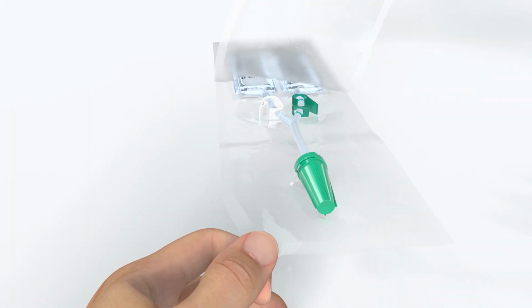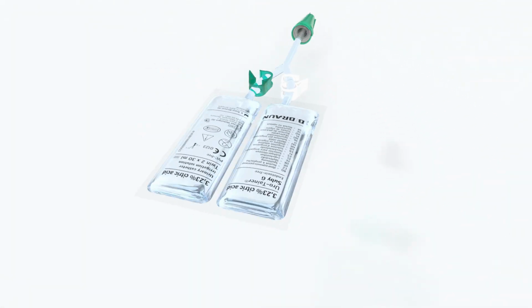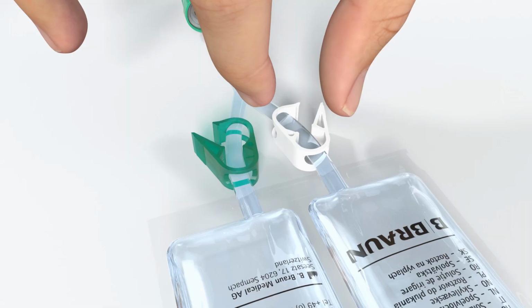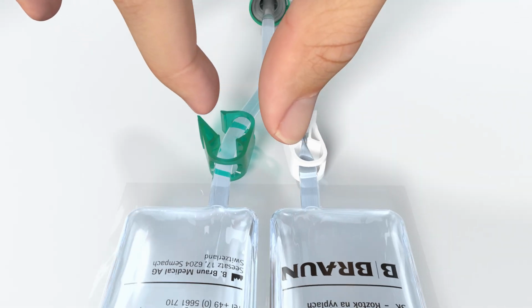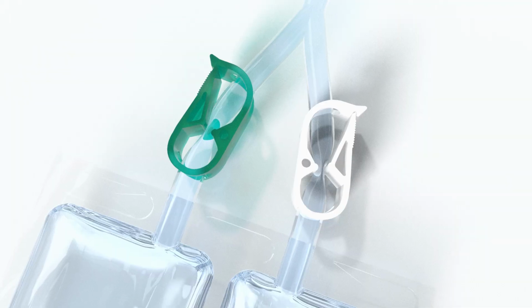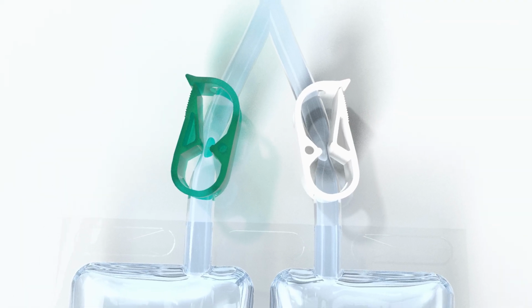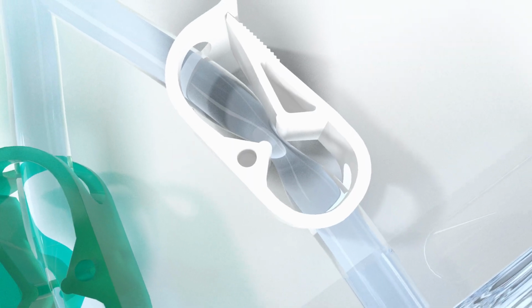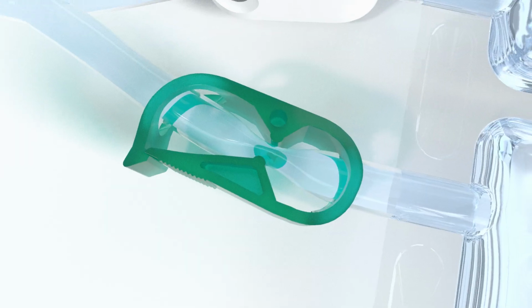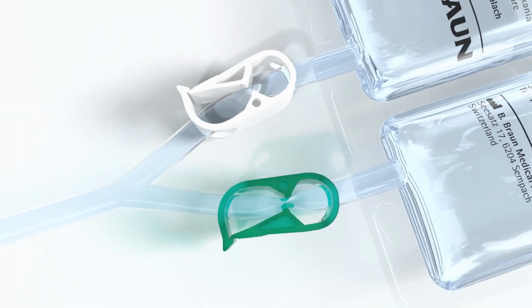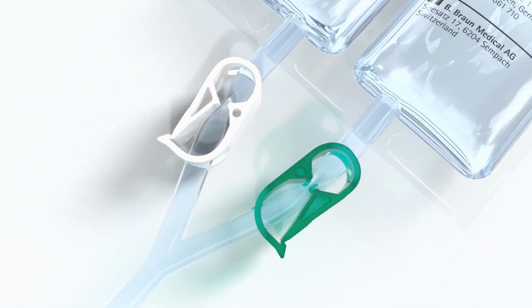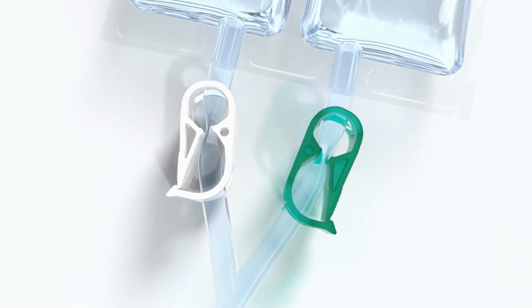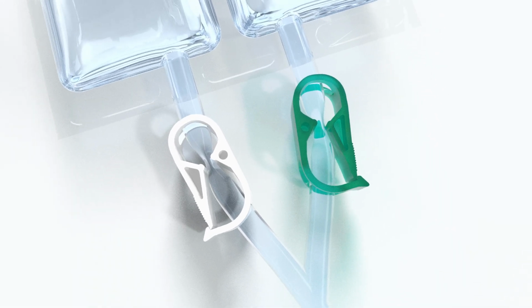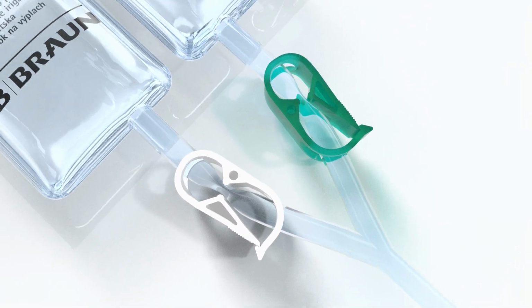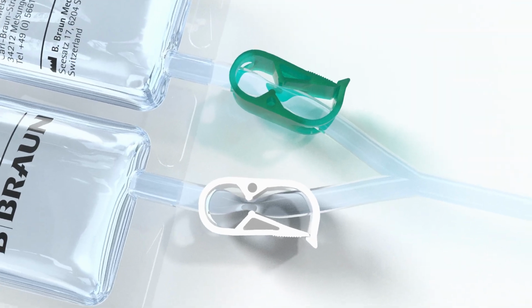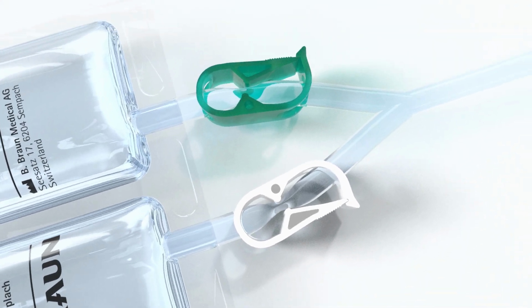Peel open the plastic overwrap and remove Uro-Tainer Suby G Twin from the sachet. Close both tubes with the white and green clamps. Please note there is 1 clamp connected to each bag, a white one and a green one. Even if the 2 bags contain the same solution, the colors of the clamp are different. The aim is to facilitate the identification of the solution first flushed compared to the second one, to ensure the same solution is not flushed twice.